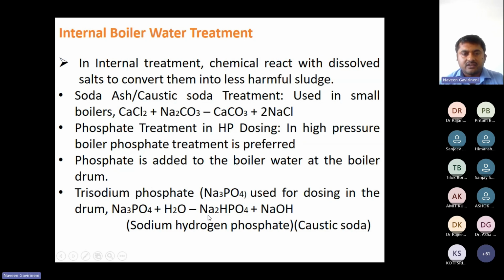Just have a look at this. We are using trisodium phosphate, Na3PO4, which reacts with water and is converted into Na2HPO4, sodium hydrogen phosphate. This has one important property: it bonds the particles. After bonding, the density of the particles increases, so they come down to the bottom of the drum. We remove them by the blowdown system. I will explain that when we come to that picture.